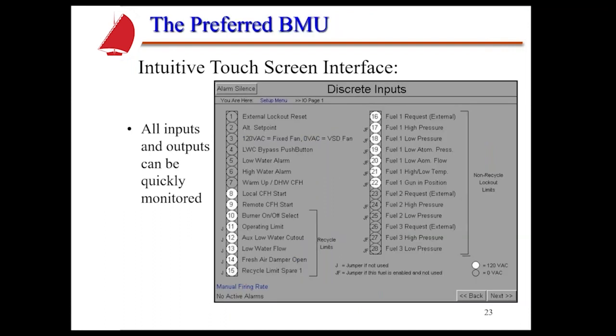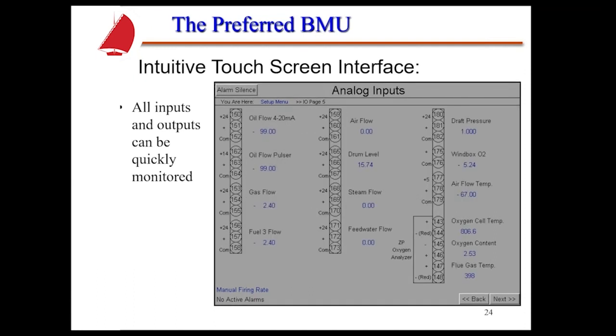And with this touch screen, we can look at all the status of, for instance, the discrete inputs. So we can see exactly what's going on with those digital inputs on this particular device. And we can tell whether they're made or they're not, obviously, and whether they're recycle or non-recycle inputs. A lot of information very quickly at a glance. Also, the analog inputs. Another screen can give us the status and where they're at on all of these analog inputs. This is a technician's dream, because instead of having to pull out a meter and interrupt a 4 to 20 or whatever, we can actually look at everything right there and it can tell us what's going on. Very, very important, very powerful screen.